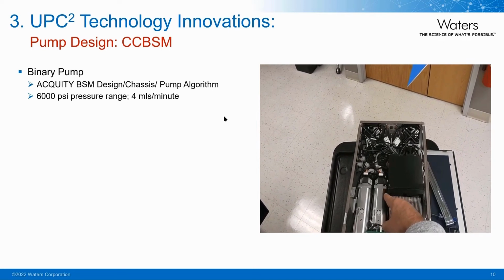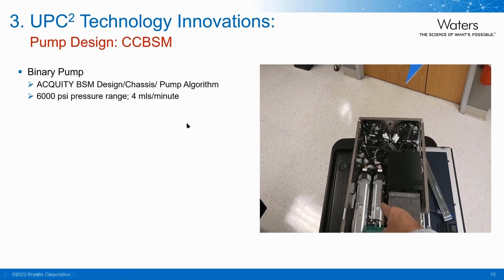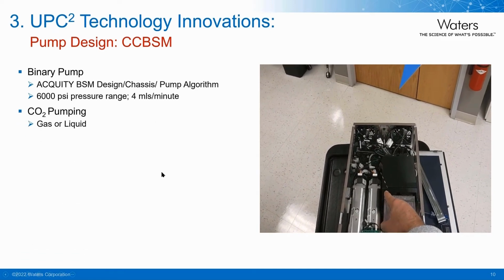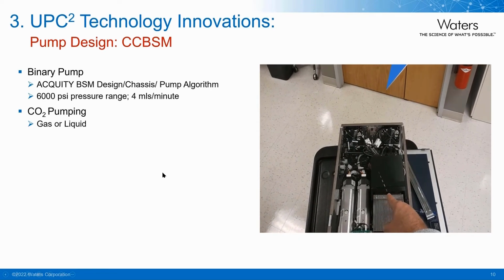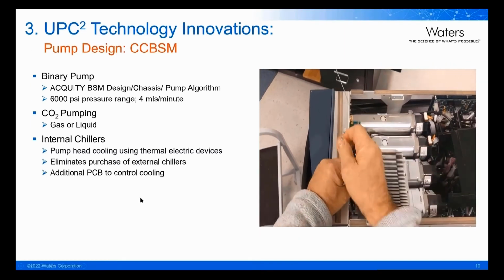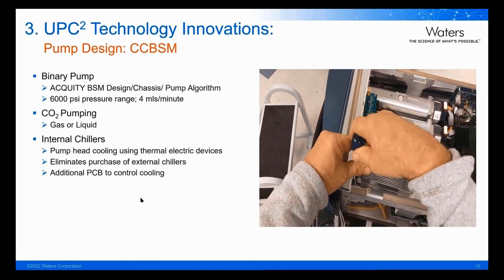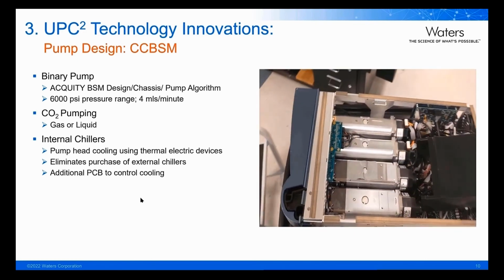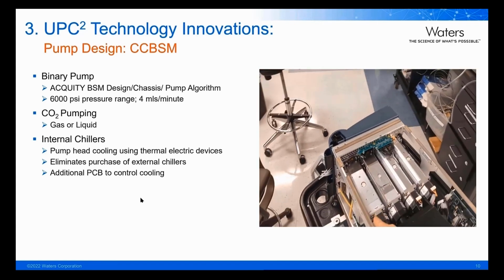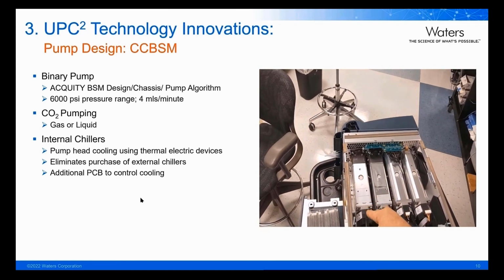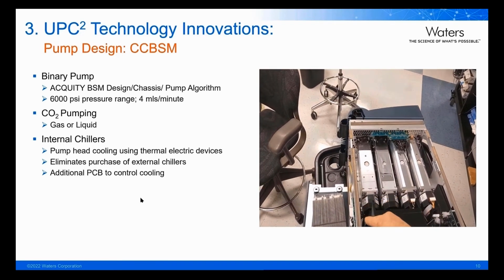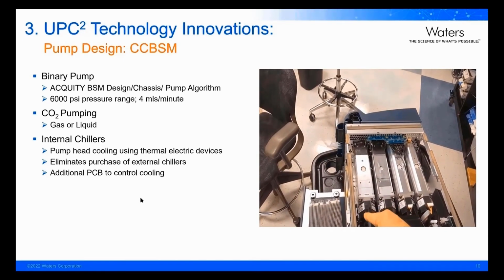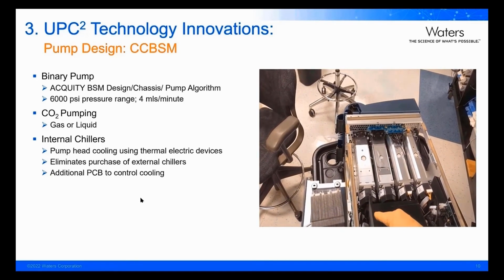Another innovation of the pump is you can do gas or liquid CO2. This is unusual as most preparative and analytical systems do require liquid CO2 only. The internal chillers, which I am showing you right now, are thermoelectric devices and eliminate the purchase of external chillers, which again saves time and money and size. We also added a PCB board for the chiller, as well as a 4-solvent select valve for co-solvent selection.